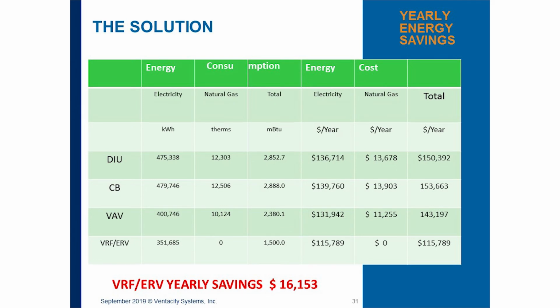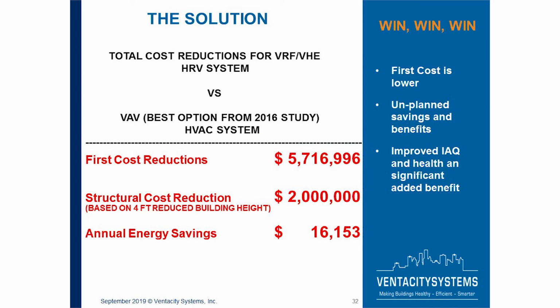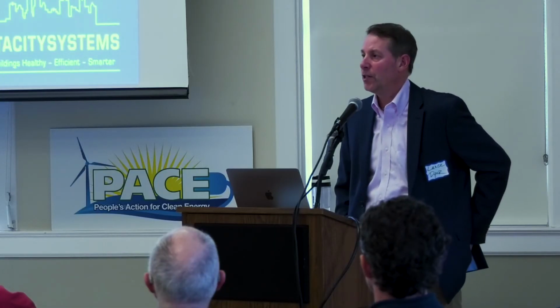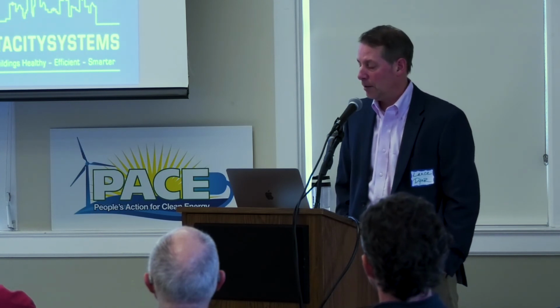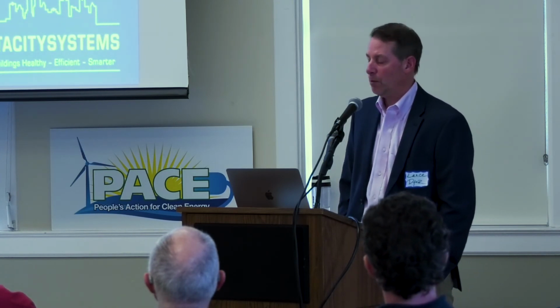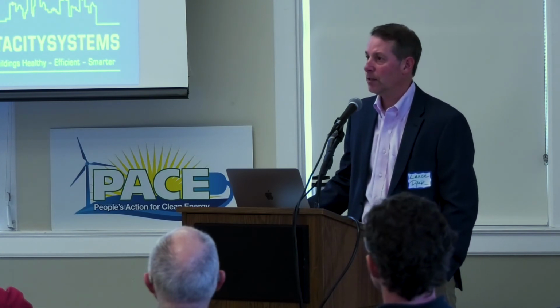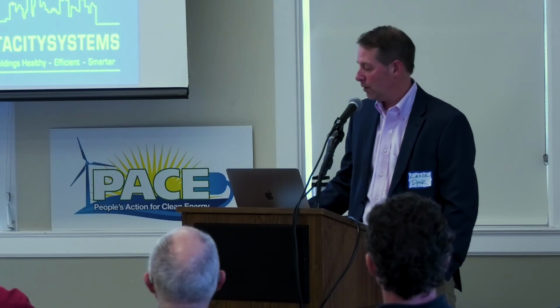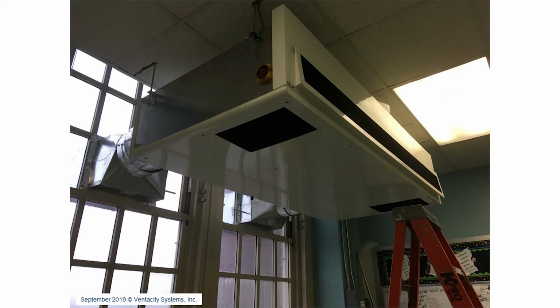Yearly energy savings is great, obviously, because we're consuming less. No gas, fossil fuels goes away. So again, you're eliminating fossil fuels altogether with this type of a combination. And you've got total reductions of the VRF ventilation system versus the best option in a 2016 study. First cost reduction of over $5 million. And this we see all the time. The upfront cost of the equipment, the operating cost of the equipment, overall annual savings, that number is something we see all the time. And that's what the unit would look like for a classroom.